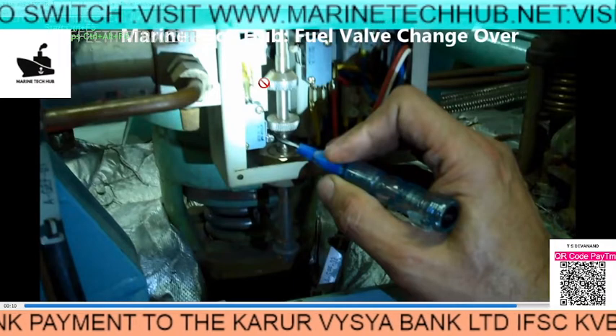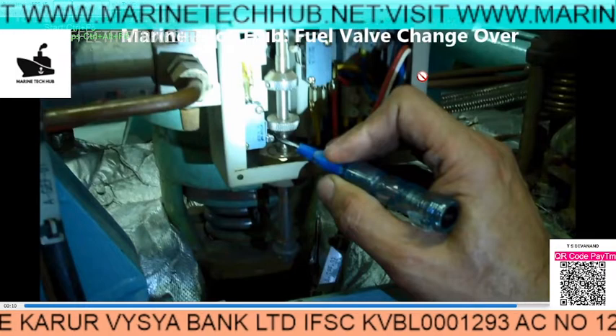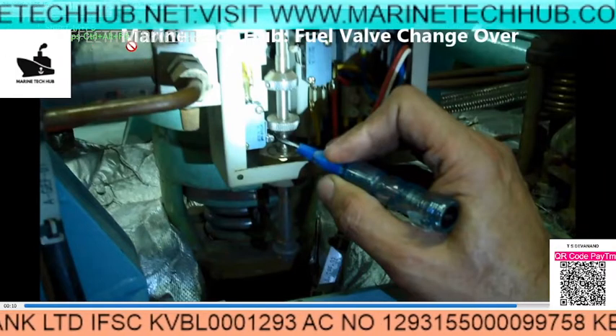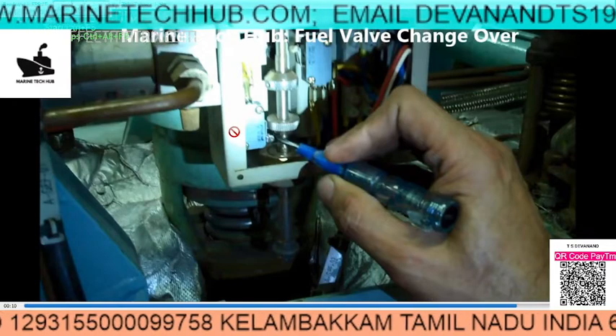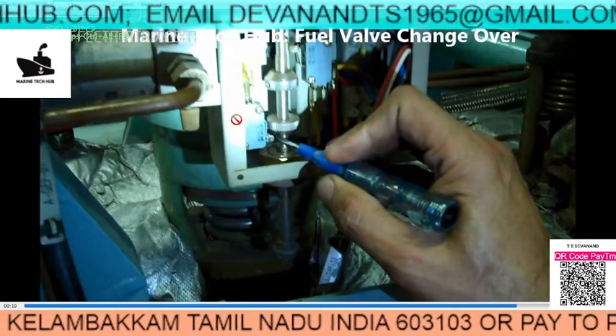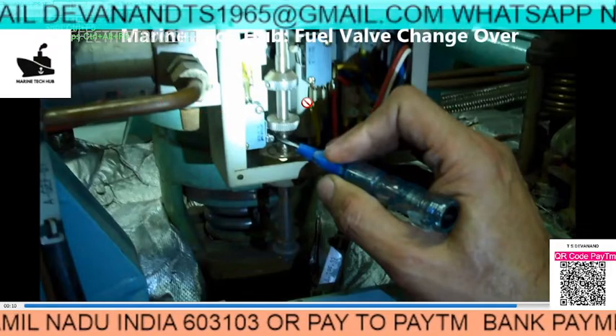Take it on load, so you are sure that one generator is on load. Keep another generator on heavy oil so that this is on the flushing pump. Then for generator number two and three, you can changeover by the normal changeover process from heavy oil to LSMGO. So in case something happens there as well, you will not go to blackout.